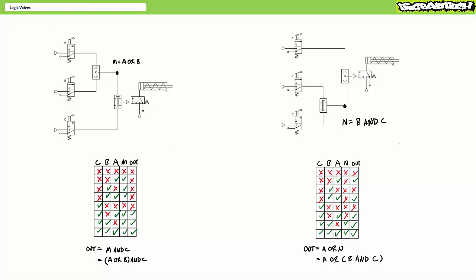In conclusion, this lecture examined pneumatic logic valves, specifically the AND or dual pressure valve and the OR or shuttle valve in their applications in pneumatic systems. We learned an AND valve produces output only when both A and B air pilot signals are present. Additionally, we learned an AND valve selects the lowest of two pressures. Similarly, we learned an OR valve produces output when either A or B air pilot signals are present. Additionally, we learned an OR valve selects the highest of two pressures. Lastly, we performed some brute force logical analysis of a couple different example air piloted pneumatic systems employing different configurations of logic valves.